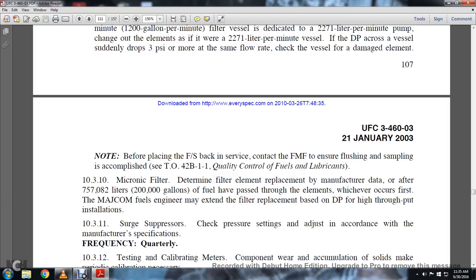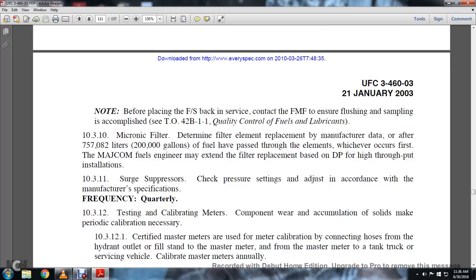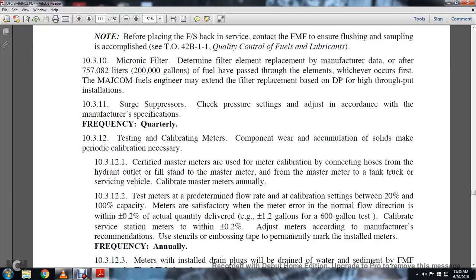10-3-10 Microfilter. Determine the filter element requirements from the manufacturer's data or after 200,000 gallons of fuel has been passed through the elements, whichever occurs first. The major command fuel engineer may extend the filter replacement based on the DP or throughput of the installation. 10-3-11 Surge suppressors. Check the pressure setting and adjust in accordance with the manufacturer's specifications. Frequency: quarterly. Alright, moving on to testing and calibrating meters. Component wear and accumulation of solids make periodic calibration necessary.